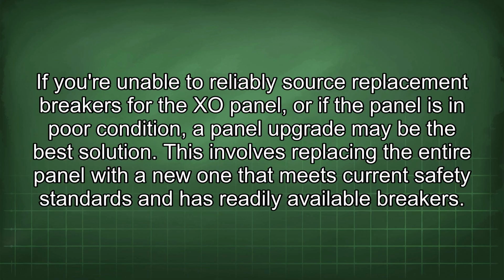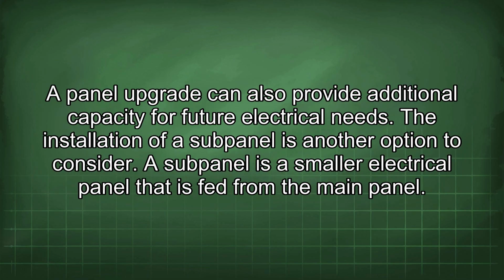When addressing these safety concerns, it's important to consider the option of upgrading the electrical panel. If you're unable to reliably source replacement breakers for the XO panel, or if the panel is in poor condition, a panel upgrade may be the best solution. This involves replacing the entire panel with a new one that meets current safety standards and has readily available breakers. A panel upgrade can also provide additional capacity for future electrical needs.